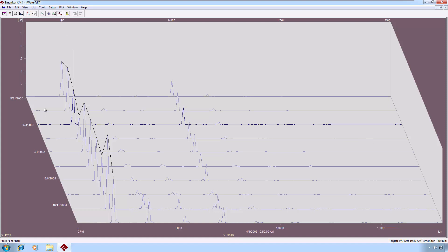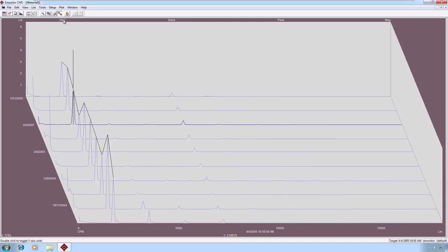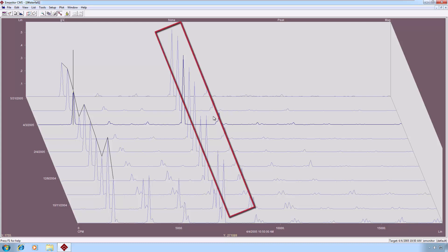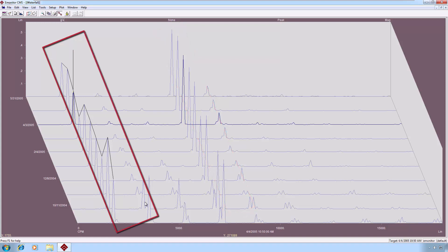Some other interesting things about this plot. As with a standard spectrum plot, the inches per second units can be toggled to scroll through different units, and the amplitude scale will rescale to reflect those units. You can also choose G's, for example, which accentuates higher frequencies and suppresses lower frequencies, often the units you will use for watching bearing defects.